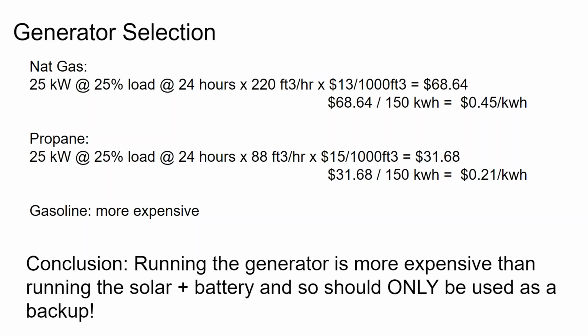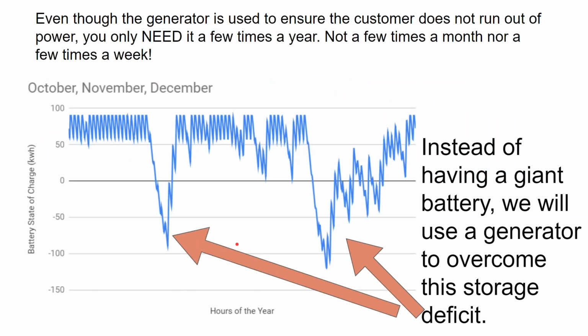So when it got down to it, it would have been better for us to just use a plain old dumb generator that we only fire up a couple of days a year to recharge the battery bank. We didn't need all the extra bells and whistles of a generator with higher power quality, less noise, variable speed output, and its own auto start control system. So just a regular house backup generator, not the renewable line, not the high-end efficient generator, just a basic generator is all you need.